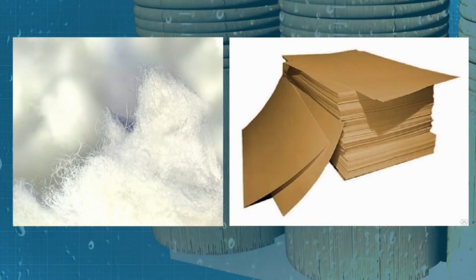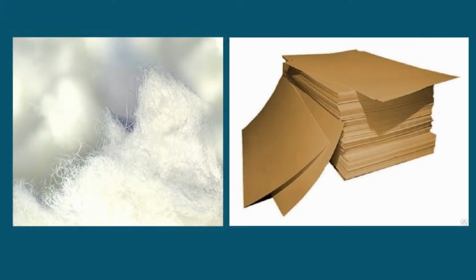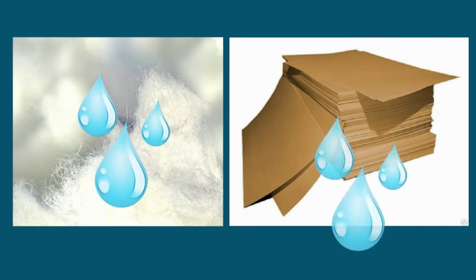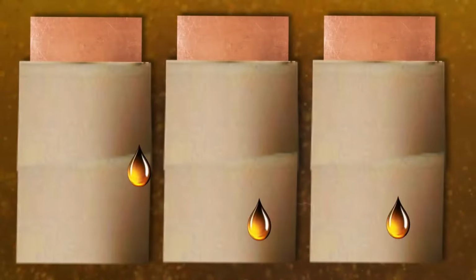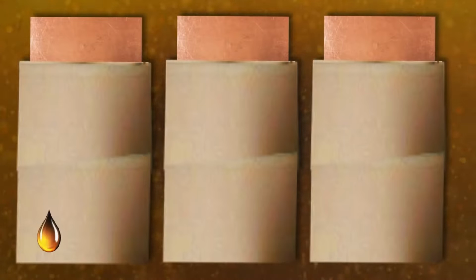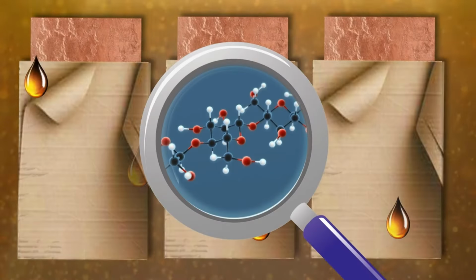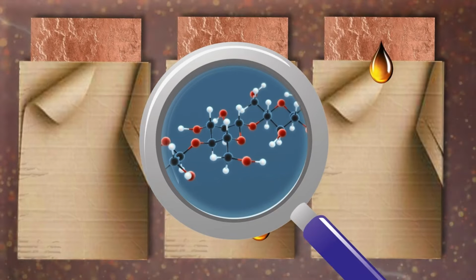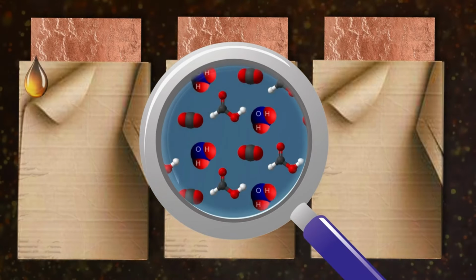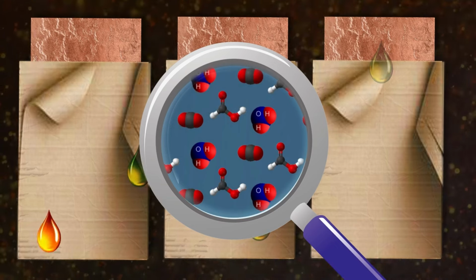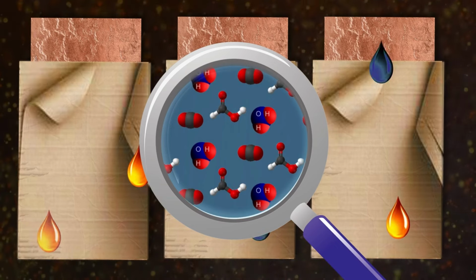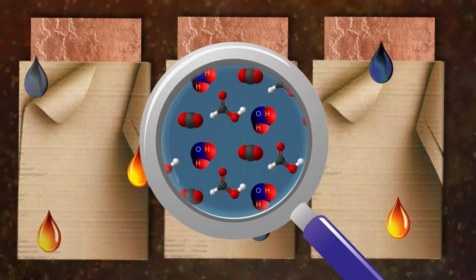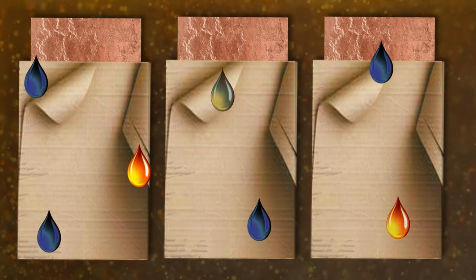Since cellulose is hygroscopic by nature, that is, has a high affinity for water, it is water that becomes the worst enemy of the solid insulation. Entering the transformer from the outside, water and high temperature destroy paper insulation for years. The cellulose molecules break down, the paper becomes brittle and loses its tensile strength. The breakdown of cellulose molecules results in formation of carbon oxide, acids and more water that again reduces the electric strength of the insulation.